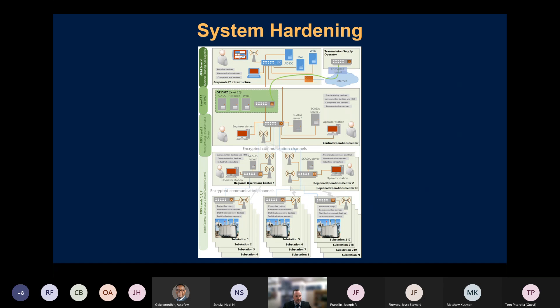Getting started on system hardening — here's an example architecture diagram. Understanding what we're building and what communication paths have to exist is always the first step. We often use a reference architecture such as the Purdue model, which is referenced here. But this should go further than just dividing the network into logical segments. We implement things at the border like very restrictive firewall rules that limit communications from host to host. The engineer should understand exactly what is required for system operation and limit communication and services to just those.